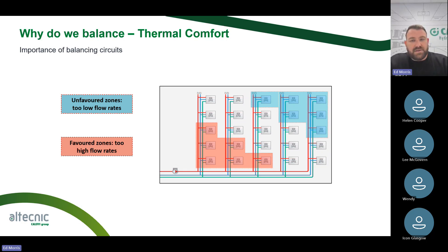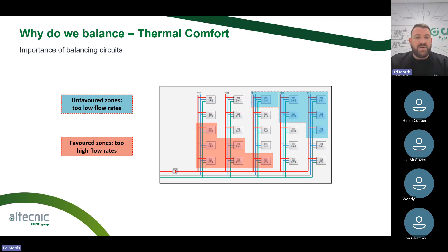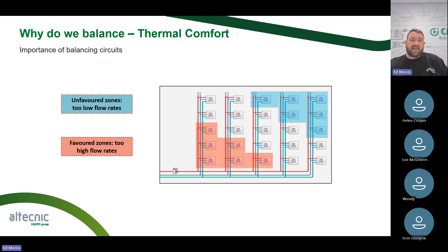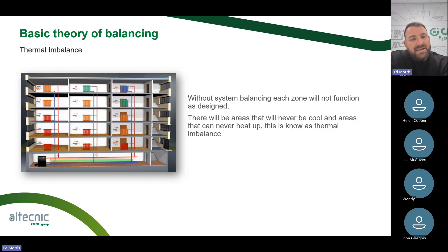There are ways we can counteract this — we need to balance the system. Generally you will see issues in a domestic property: if your boiler is situated in the kitchen, the kitchen and living room will probably get really good heat, but a bedroom further away from the boiler may not get as hot while the radiators downstairs are really warm. We need to slow the water going to the closer zones and push it to those more distant zones. Without system balancing, each zone will not function as designed, and there will be areas that never cool and areas that never heat up — this is what we know as thermal imbalances.